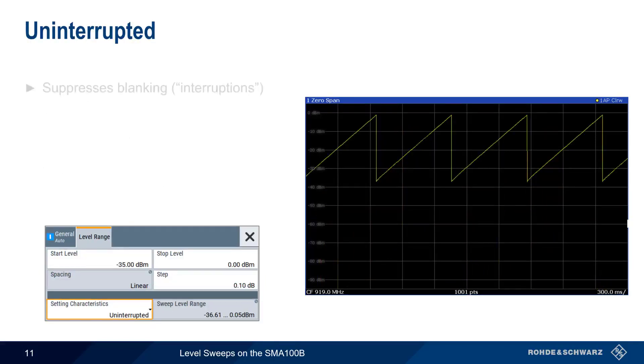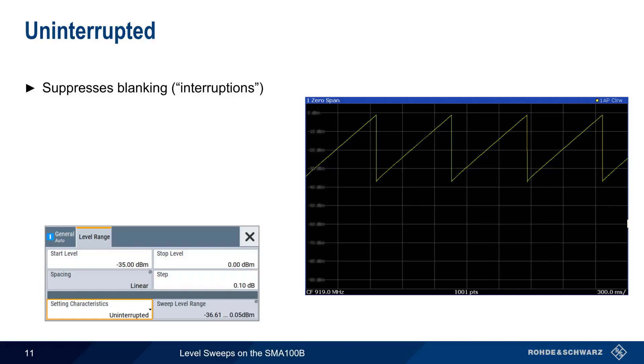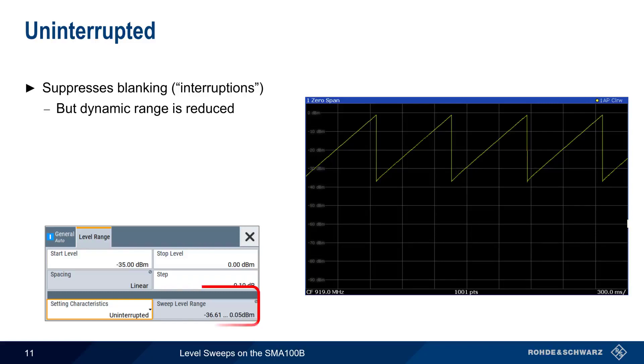As the name implies, Uninterrupted mode suppresses blanking or interruptions. Looking at the zero span trace, we don't see the same dropouts that we just saw in Auto mode. However, this mode also reduces the dynamic or swept level range. In Auto mode, our level range was about 85 dB, whereas in Uninterrupted mode, the level range is now only about 35 dB.